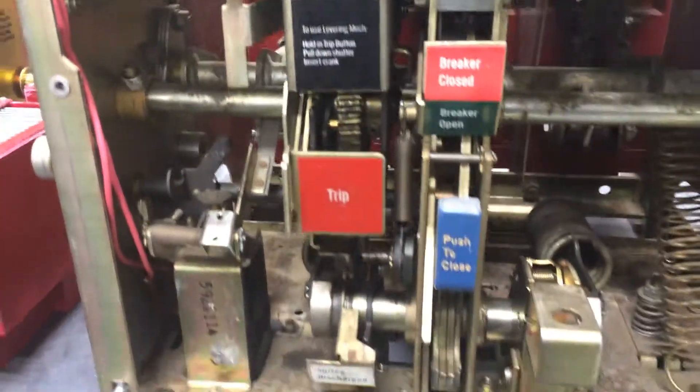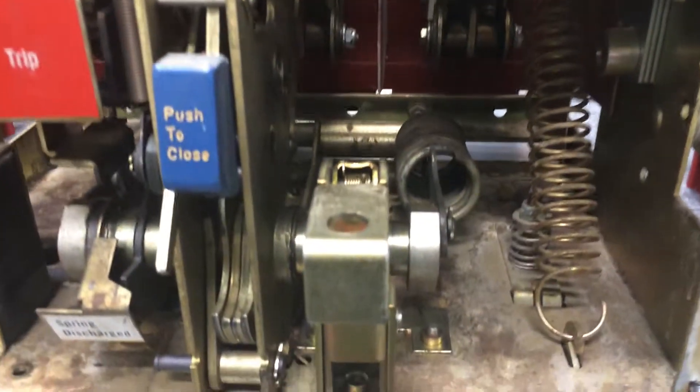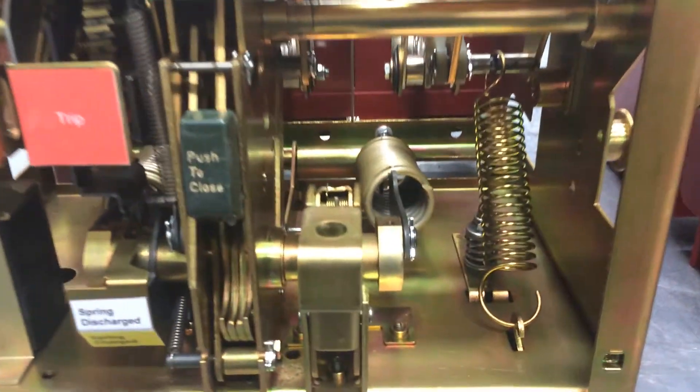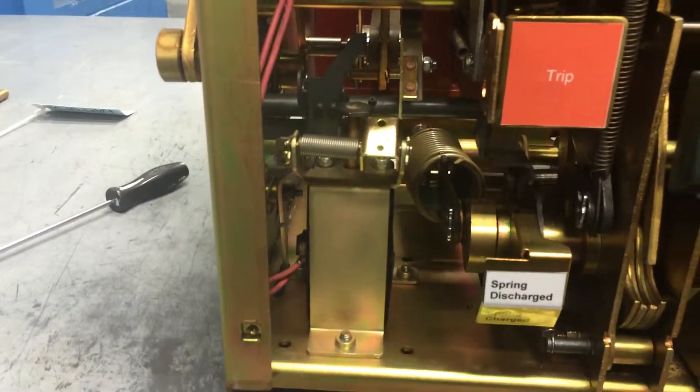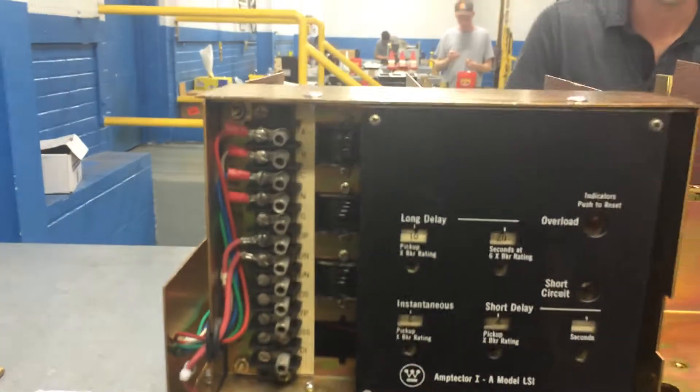Take a look at this one. Behind the cover — that's what your breakers could look like. But if you want to take a look at perfection, this is perfection right here. This is what a Class A recondition is. It's completely torn down, replated with aircraft plating, built back up, new hardware, completely tested, with a one-year warranty. That's what you get here.